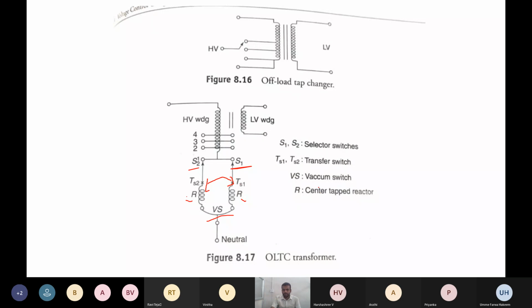So vacuum switch, what is the necessity of vacuum switch here? So vacuum switch acts like a circuit breaker. Previously I have told that the selector switches are not used for breaking or making of any switches. They are only to contact different positions in the HV winding. But here the vacuum switches will act like a circuit breaker. So these vacuum switches will be used for making or breaking of any switches or any circuit. Okay. So during tap changing, everything will be done during the tap changing only.